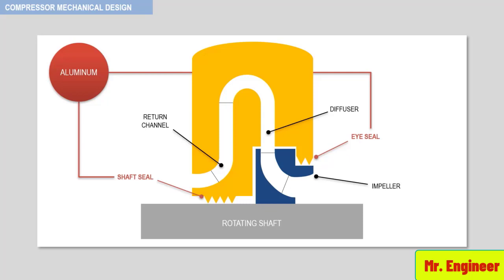Various abradable material interstage seals are also used. Abradable seals allow for contact with the rotor without causing excitation to the rotor system. This type of interstage sealing system had its origin in the aircraft engine industry. The advantage of an abradable seal is increased efficiency.